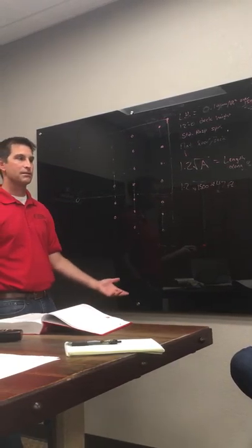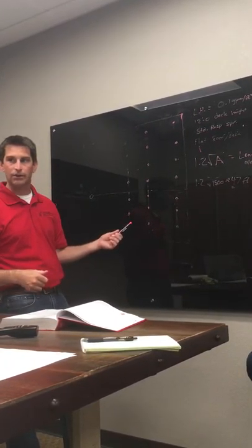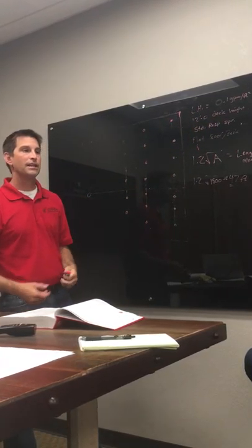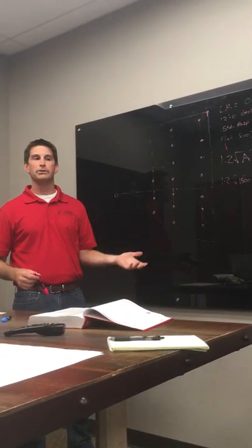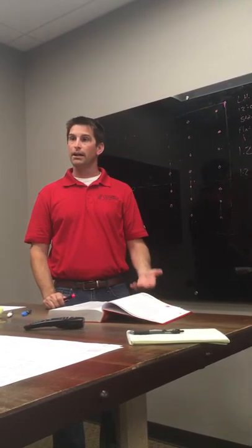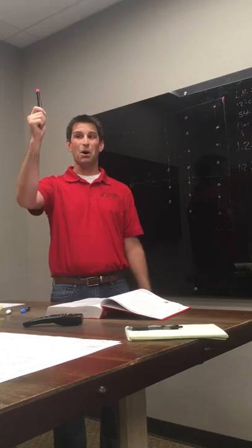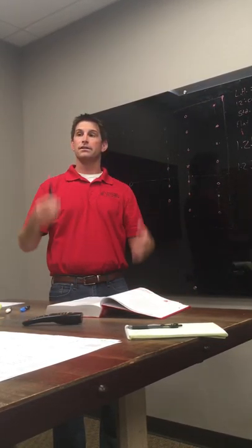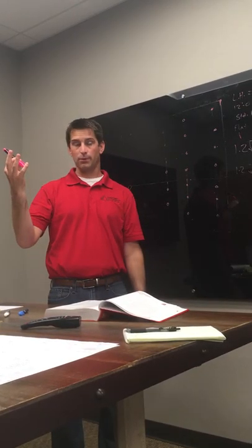Okay. Because it's going to control faster. The fire's not going to grow as big, so it's not going to get to 1,500. It's going to be smaller. But there are things that affect that, too, because I could have a quick response sprinkler in this room with a 9 or 10-foot ceiling, and if a fire starts here, that's going to go off real fast, because the fire's right here. The heat's going to go to the ceiling, and it's going to trigger that sprinkler quickly.